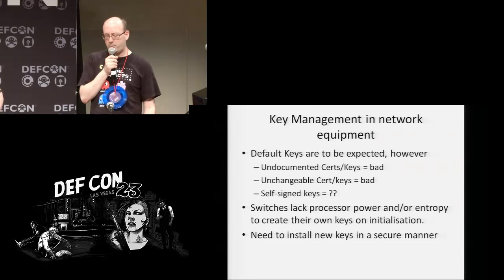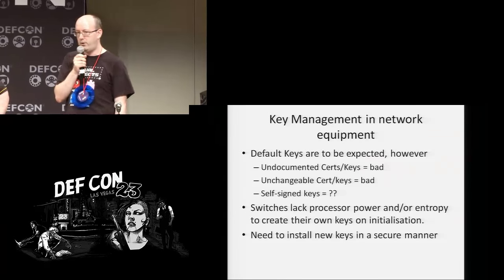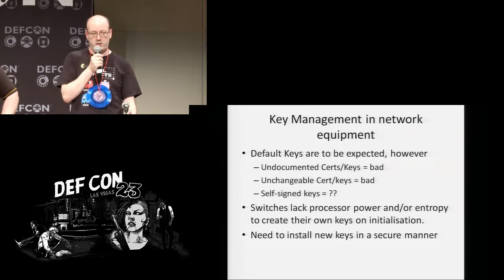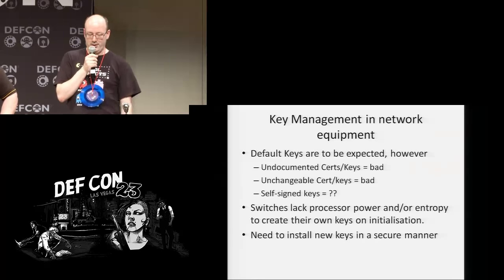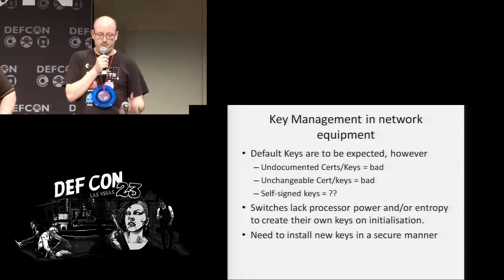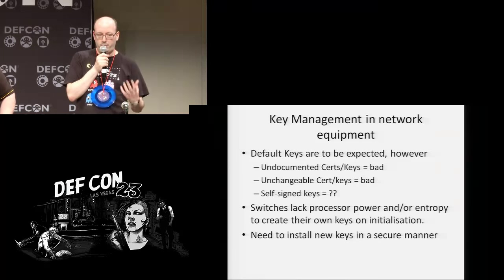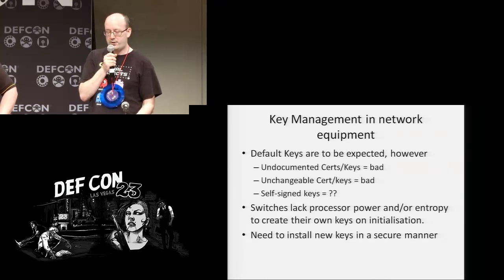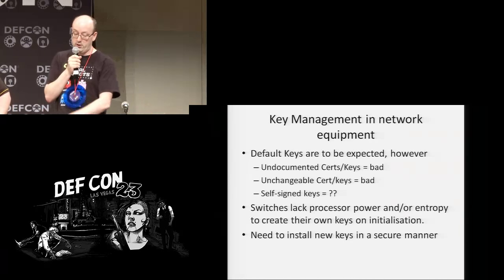Key management in network equipment: you are going to find default keys all over the place. If they're undocumented, that is bad. If they're unchangeable, that is worse — we have not found unchangeable keys, but other people looking at switches have. Self-signed keys are a more confusing issue: yes, you have self-signed keys but you lack the ability to revoke them. But in an isolated network environment that's acceptable, since you shouldn't be connecting your industrial system to the rest of the world just for VeriSign to verify your certificate. These switches tend to lack processing power and entropy to create their own keys, so vendors need to consider an initial setup process that locks things down from the start rather than having one key that talks to every switch.